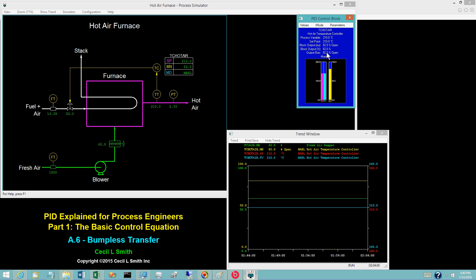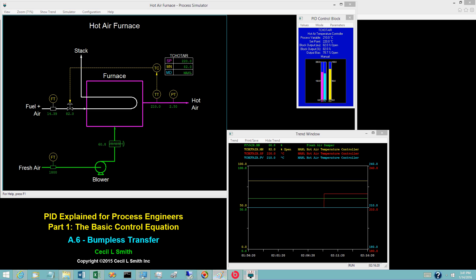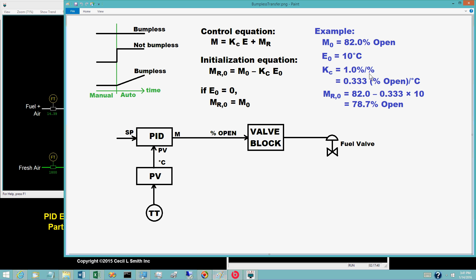The next video explains a feature known as PV tracking, which is disabled in the hot air temperature controller. Right-click the value of the setpoint and enter 220. The control error e is now 10 degrees Celsius. The point window displays a value of 78.7 percent open for the controller output bias, which is a result of the initialization calculations. As will be explained in a subsequent video, a controller gain of 1.0 percent-to-percent is a gain in engineering units of 0.333 percent open per degree Celsius.